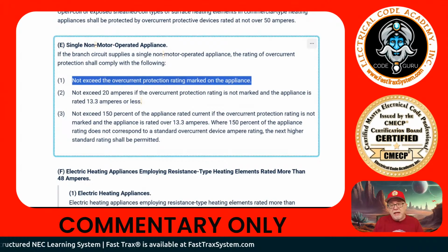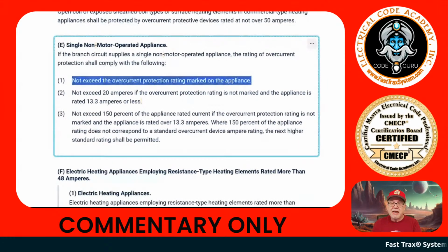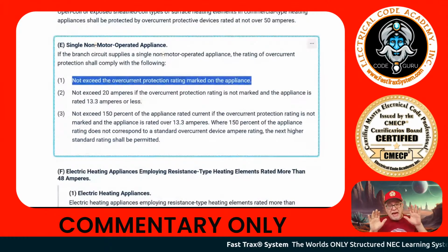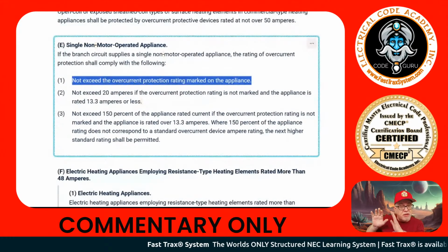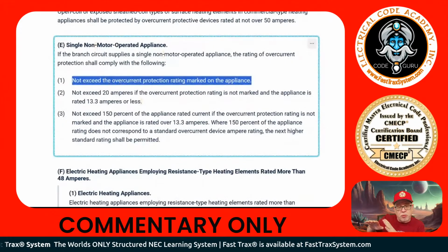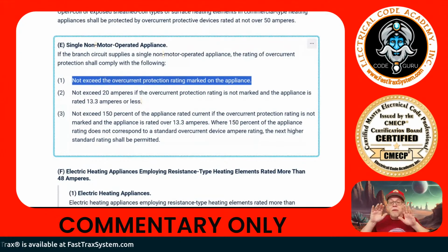All it gave us was 4,500 watts, and it gave us the voltage. Okay, so we can do a little math real quick. So we had 4,500 watts. Here's a calculator, right? And I'm going to divide that by 240. And that was 18.75. Okay, so that's our amps for that 4,500. Now, we're not doing the application for the 120 gallon or less where you do 125%. That's not part of this question. So stay with me. Not part of the question.